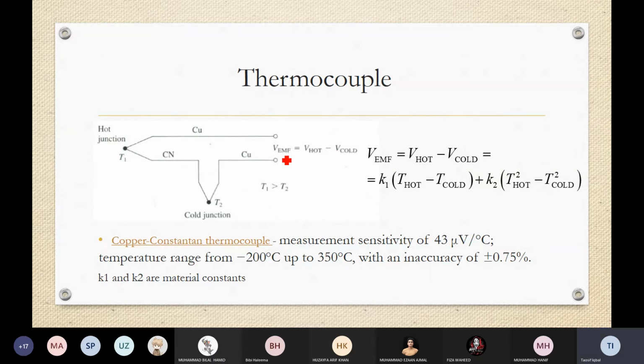Okay, so now we can find out the voltage drop across this copper to copper metal connection, and that is going to be the difference between the hot junction voltage or temperature and the cold junction voltage or temperature. So how can we find the hot side voltage? We are going to open the junction which is placed in the hot environment and then measure the voltage. And because that is not possible, we are going to approximate that voltage V hot by detecting the temperature over there, and that is going to be like this.